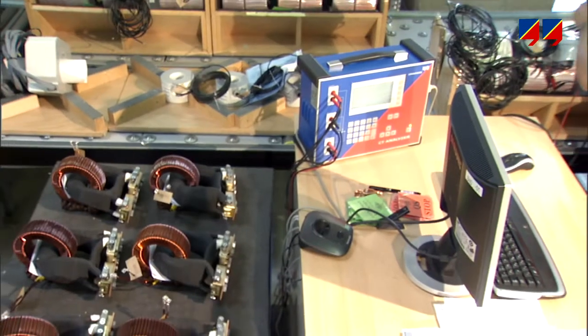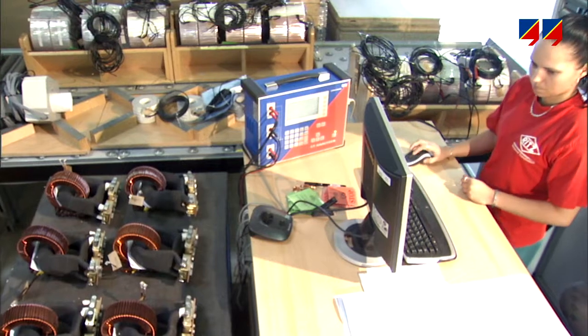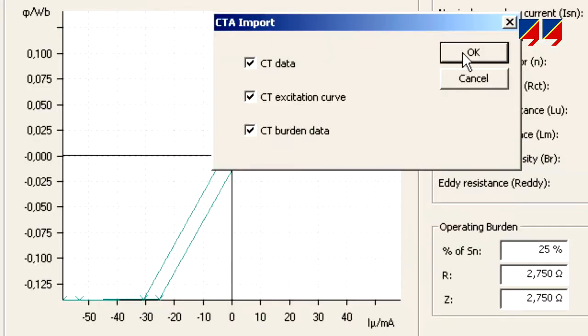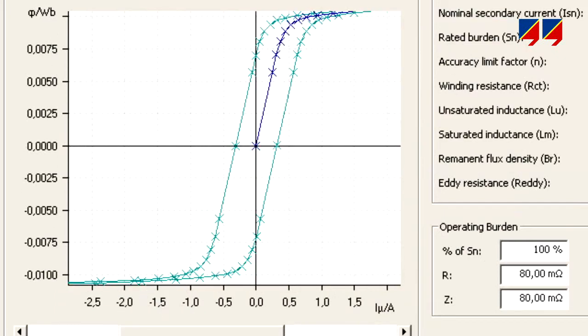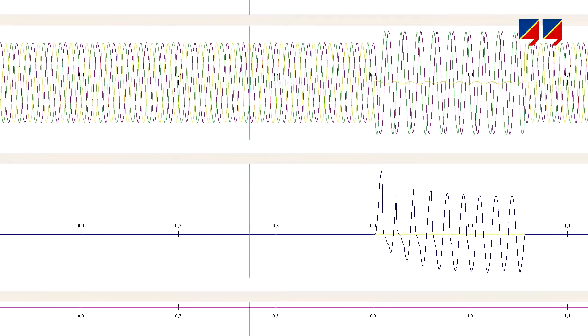CT analyzer can also be operated via PC or laptop, allowing the convenience of working with a mouse and keyboard. The parameters of a measured CT can also be exported to network simulation programs, allowing them to calculate electrical fault currents based on the actual CT behavior.